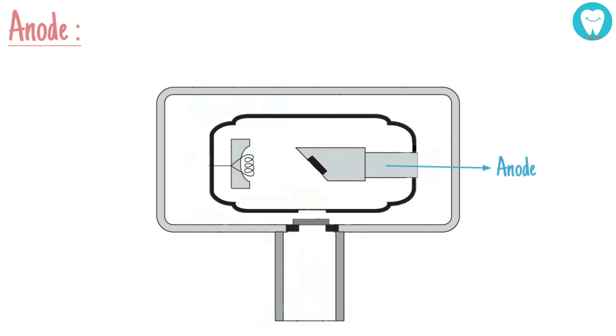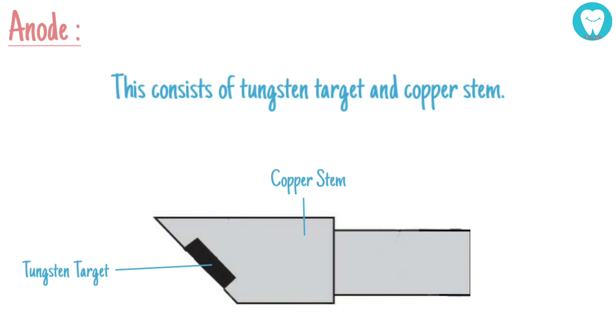Now let's take a look at the anode. This consists of a tungsten target and a copper stem. In a stationary anode, the tungsten target is in the form of a circular disc about 1 mm thick and 1 centimeter in diameter.